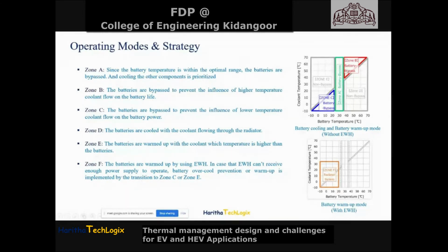And zone B, where is it? It is the zone where the battery temperature is more than 35 degrees Celsius up to 70 degrees Celsius, but the coolant temperature is already in a hot area too. So in this case, the batteries are bypassed to prevent the influence of high temperature coolant flow, because the battery is already at high temperature and the coolant is also at high temperature. If the coolant circulates, it will further worsen the temperature of the battery pack. So in this case also, battery bypass happens to avoid the influence of coolant temperature on the battery pack temperature. This is battery bypass again, but in zone B.